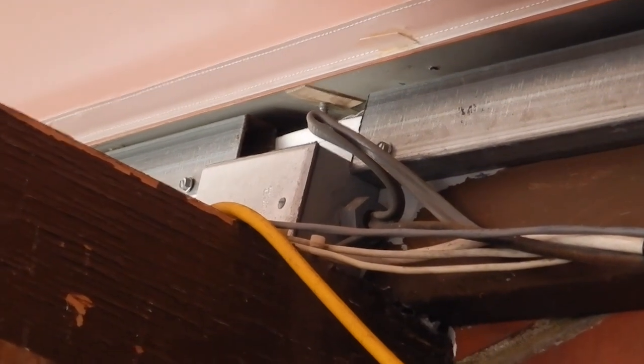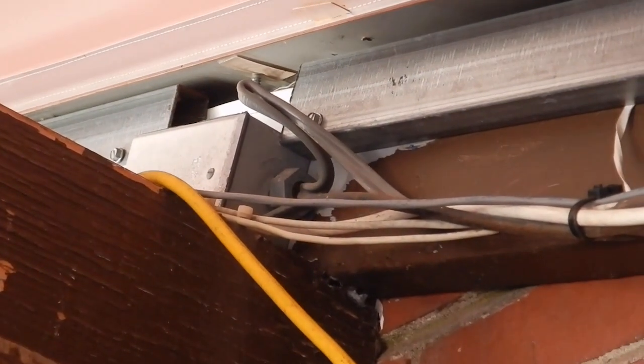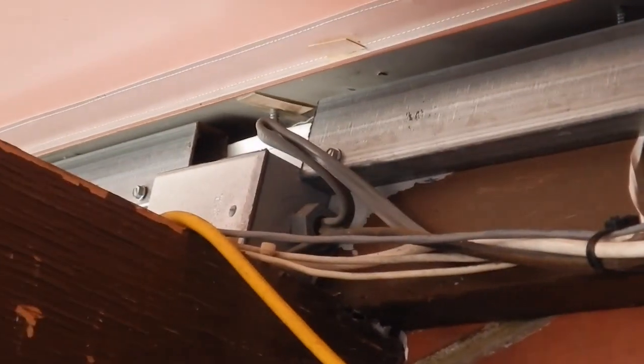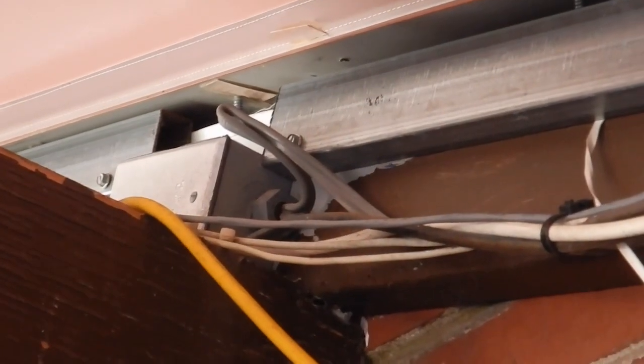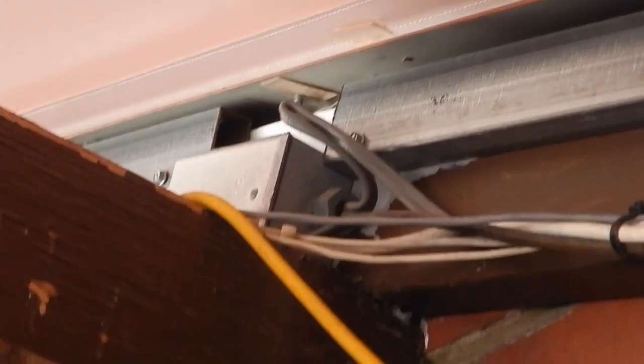I think that cable is most likely damaged. One of the other problems I see is there are two cables going into that connector. I'm willing to bet that's a violation of section 110.3b. I doubt that connector is listed for having two cables in it.